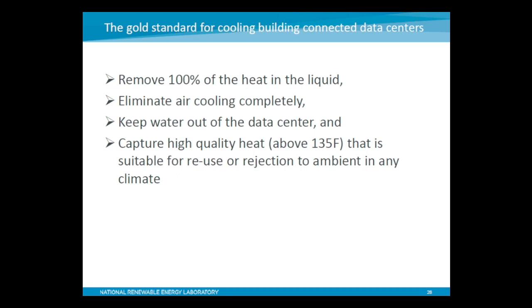So what would be the gold standard for building connected data centers? We'd like to remove 100% of the heat with liquid and eliminate air cooling completely, keep water out of the data center, and capture heat above 135 degrees Fahrenheit, high enough quality that it's suitable for easy rejection outside without mechanical cooling equipment, or hot enough to be reused in a building's hot water or air heating system in cold climates.